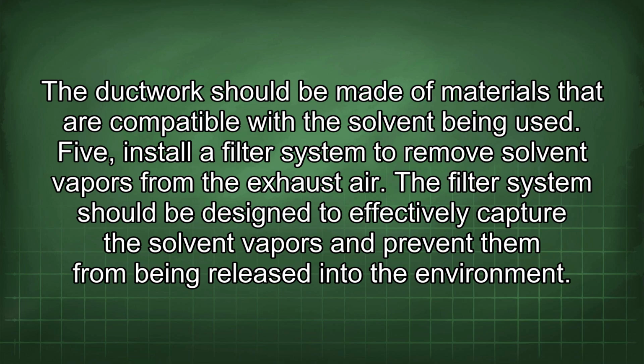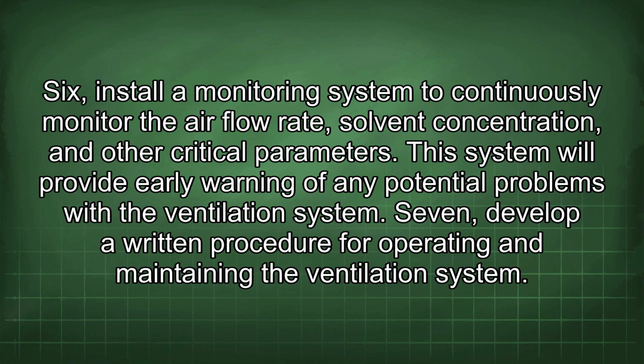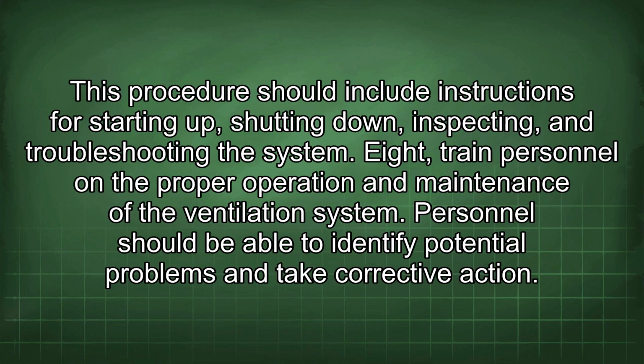5. Install a filter system to remove solvent vapors from the exhaust air. The filter system should be designed to effectively capture the solvent vapors and prevent them from being released into the environment. 6. Install a monitoring system to continuously monitor the airflow rate, solvent concentration, and other critical parameters. This system will provide early warning of any potential problems with the ventilation system. 7. Develop a written procedure for operating and maintaining the ventilation system. This procedure should include instructions for starting up, shutting down, inspecting, and troubleshooting the system.